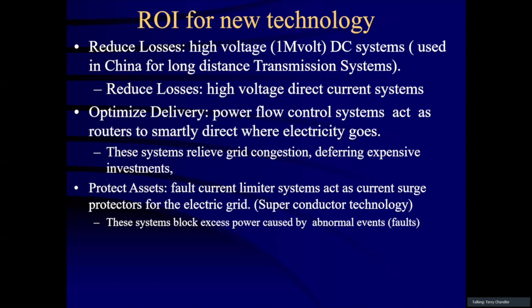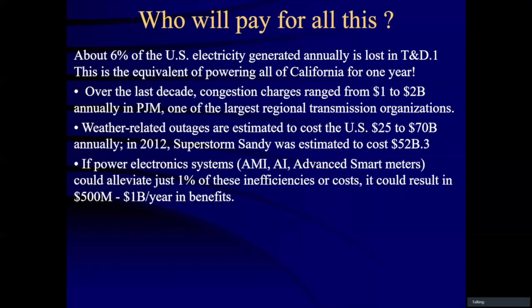There's a little bit of a misnomer in some of the advertising for those. These superconductor technology switches limit the power if there's a fault. So you can think of them as a fuse that opens, but it doesn't really open. And it happens very quickly with a superconductor. And so it blocks the power until the fault can be manually cleared with a breaker or a switch.